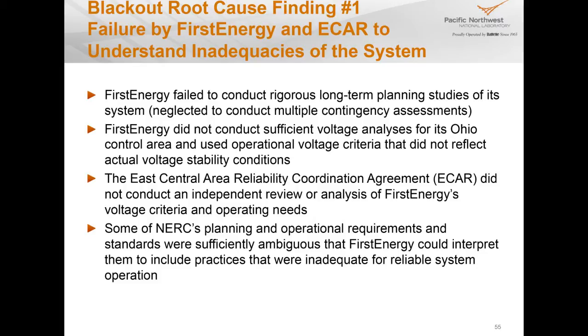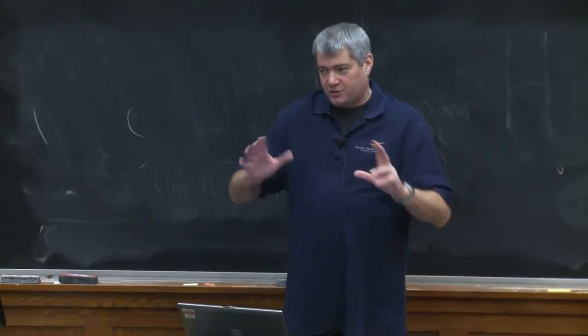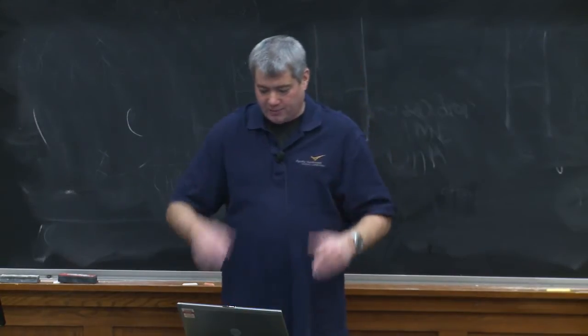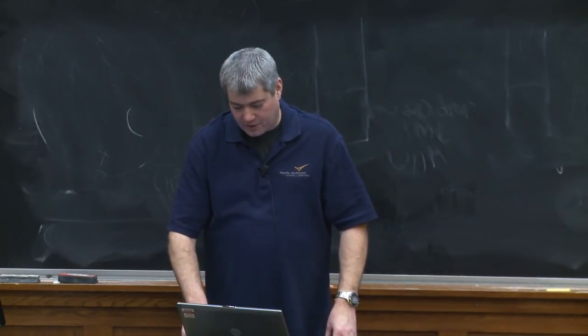I'd subtitle this lack of institutional memory. Studies done back in the 80s by the predecessor utilities said that if you operate the grid in such a way, it could set up a sequence of events that could cause this kind of thing to happen. So, to prevent that, maintain voltages at certain places above certain limits. They had forgotten about that previous engineering work.